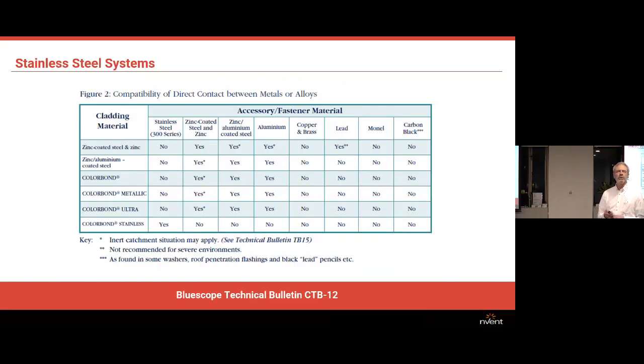And this is a table showing compatibility between different roof materials from the supplier and materials of lightning protection products. So they're saying there that for zinc aluminum, second line down, zinc aluminum or aluminium coated steel, you can use zinc coated steel and zinc materials on it. You can use aluminium materials on it, but you can't use bare copper or brass on it. Traditionally, people think of lightning protection systems being made of copper, so it's good to keep this in mind, that's not necessarily the case.